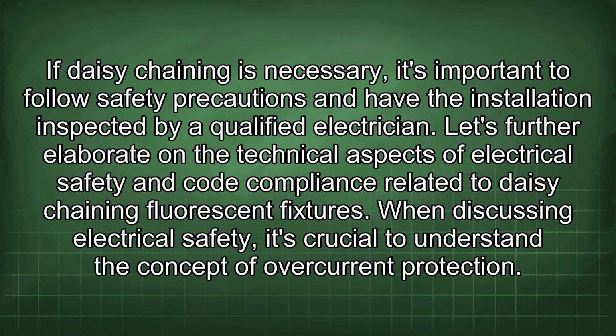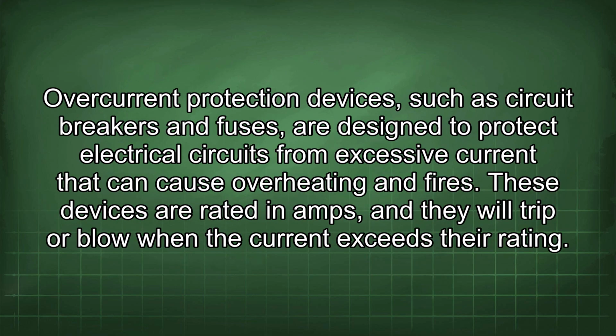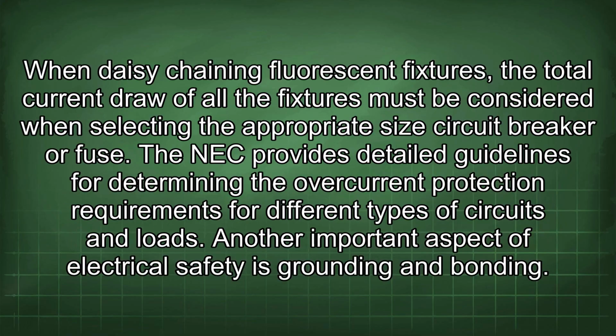Let's further elaborate on the technical aspects of electrical safety and code compliance related to daisy chaining fluorescent fixtures. When discussing electrical safety, it's crucial to understand the concept of overcurrent protection. Overcurrent protection devices, such as circuit breakers and fuses, are designed to protect electrical circuits from excessive current that can cause overheating and fires. These devices are rated in amps, and they will trip or blow when the current exceeds their rating. When daisy chaining fluorescent fixtures, the total current draw of all the fixtures must be considered when selecting the appropriate size circuit breaker or fuse.